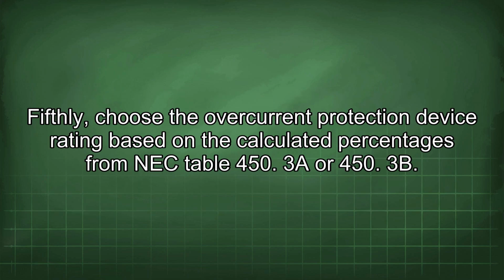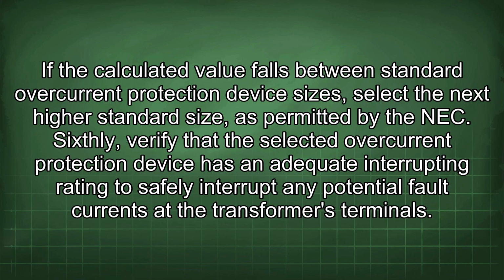Fifthly, choose the overcurrent protection device rating based on the calculated percentages from NEC Table 450.3A or 450.3B. If the calculated value falls between standard overcurrent protection device sizes, select the next higher standard size, as permitted by the NEC.